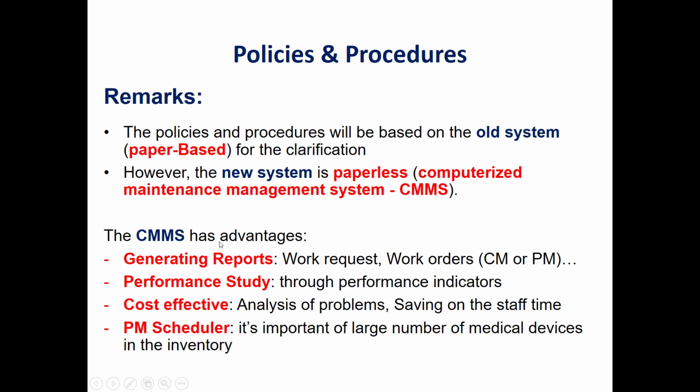One of the major advantages of the computerized system is that we can easily generate reports to compare, for example, the current year with the previous years, concerning, for example, the number of corrective maintenance work orders, or the percentage of pending work orders generally, whether related to corrective maintenance or preventive maintenance, to study the performance within the department.